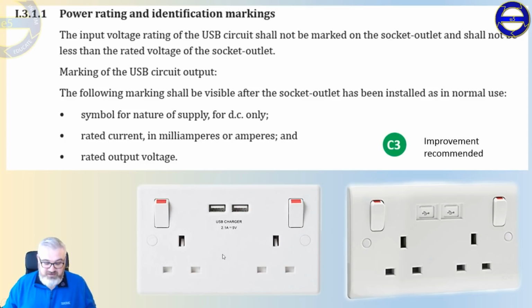So as the inspector, if I was going around and I found this device here, I would then give a C3 for improvement recommended. Why? Because it's out of scope of the wiring regulations, which I know I don't have to, but as a diligent inspector, as a competent inspector, these are issues which I may wish to highlight to my client. Now, as a client, I can tell you now, I would go, yeah, okay, I'm not too fussed. However, I would start looking into these, because we all just assume that these are fully compliant with the requirements of all the standards.